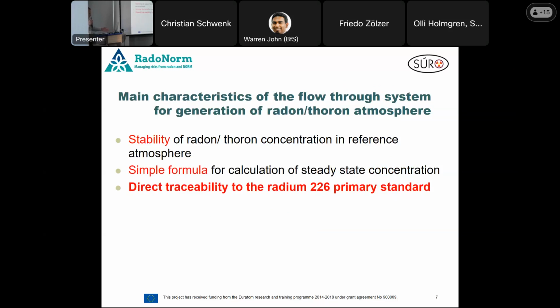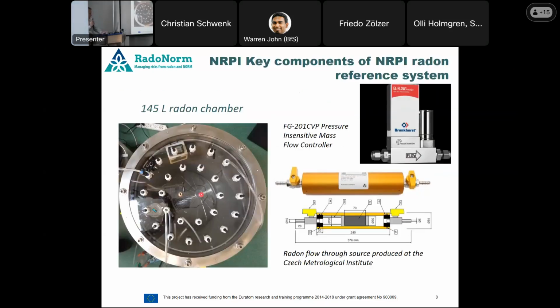This arrangement gave the possibility of device testing at low activity concentration and the possibility of long-time tests. The main advantages of the flow-through system are stability, a simple formula for calculation of steady-state concentration, and direct traceability to the radon primary standard. This is a picture of the setup.